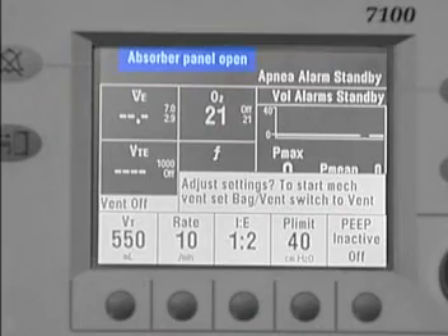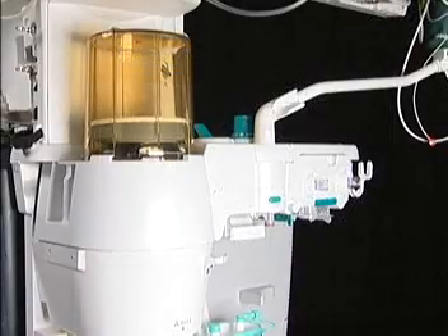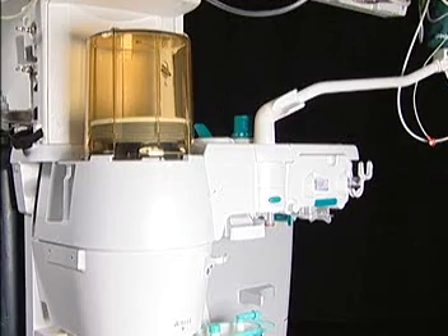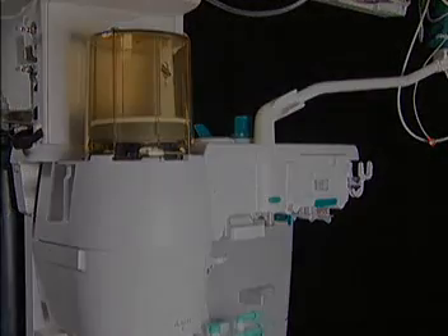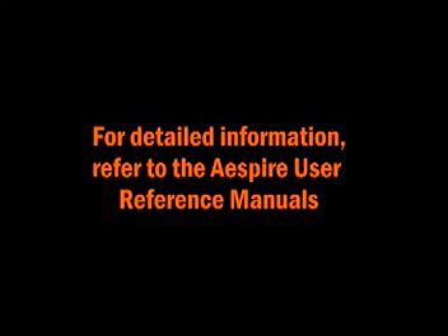Note, if the ABS is not fully engaged, the absorber panel open message will appear on the 7100 ventilator display. Be sure to conduct the leak tests outlined in your user reference manual following the removal and replacement of the ABS.